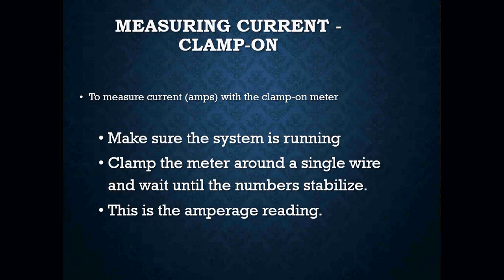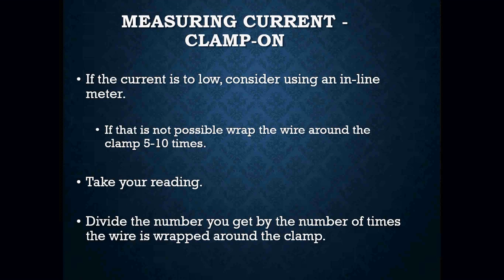So to measure current with a clamp-on meter, make sure the system is running and on. Clamp the meter around a single wire and wait until the number stabilizes. You cannot take an amperage reading on more than one wire at a time. If you put a bunch of wires inside the clamp, all it's going to do is cancel out and you're going to read 0. Okay, so make sure that you have one wire at a time. Wait for that number to stabilize and then you will have an amperage reading.